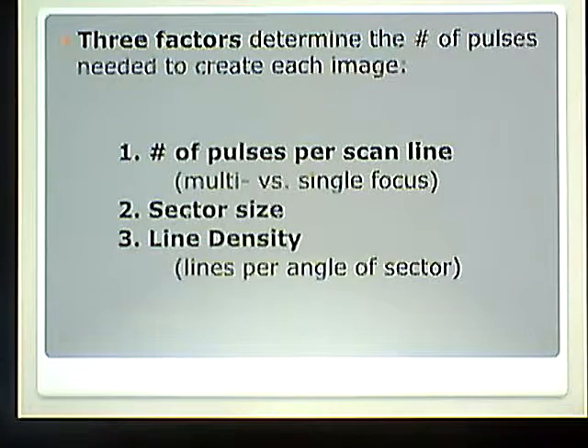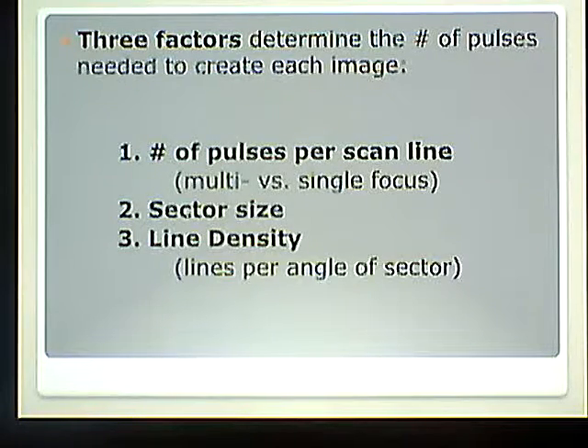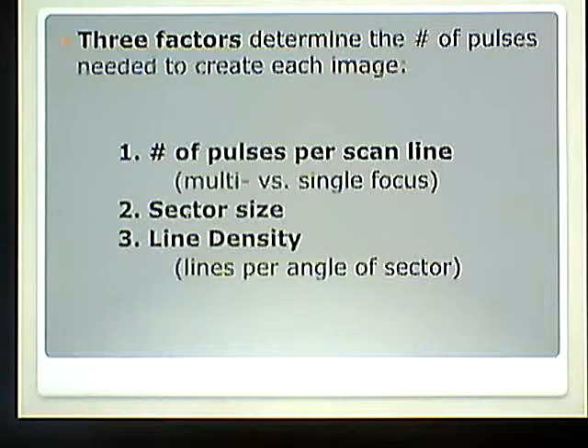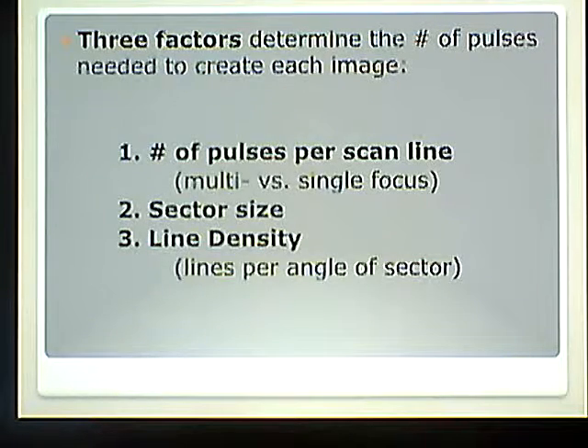There are three factors that determine the number of pulses needed to create each image. Number one is the number of pulses per scan line — remember we have multi versus single focus. Number two is the sector size. Number three is the line density, which refers to the lines per angle of sector.